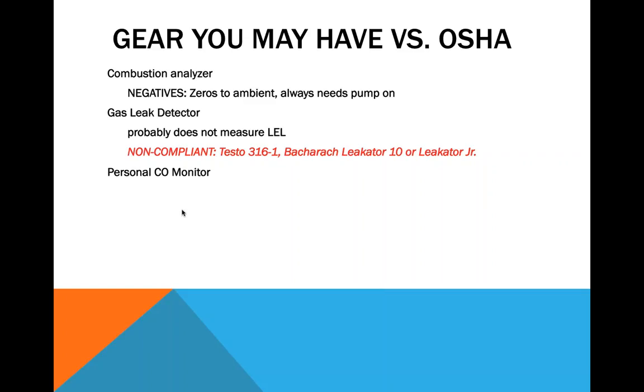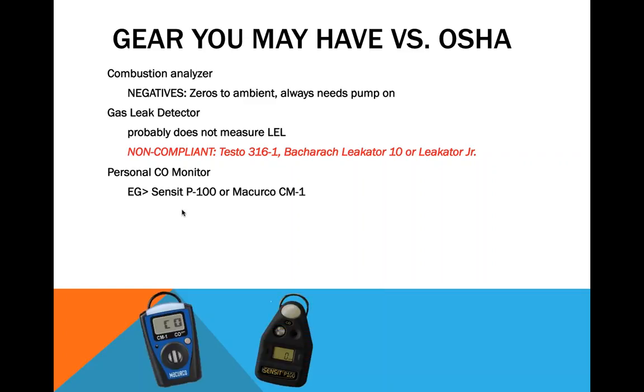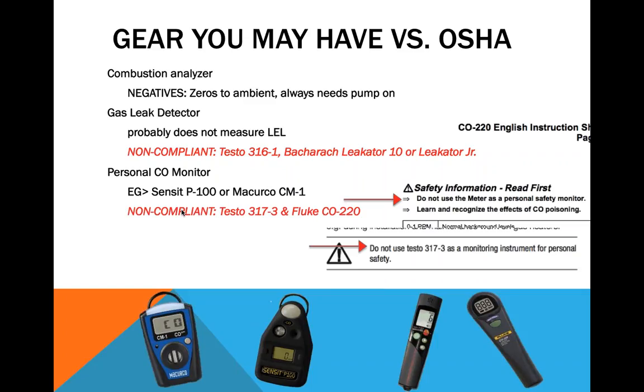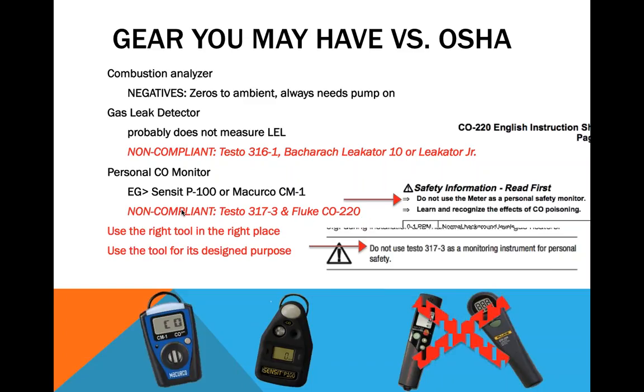Your personal CO monitor, your ambient CO monitor, things like the Sensit or the Macurco, these small devices are purpose-built for personal safety monitoring. They have lights, vibrating alarms, and audible alarms. They're designed to be rugged and used in the field for personal monitoring for CO. Non-compliant products like the Testo 317 and Fluke CO220 may not be used as a personal safety monitor. You can see here excerpts from the instruction manuals of these two products stating they're not to be used as a personal safety monitor. They can be used for ambient air detection, but not for personal monitoring. So the bottom line is use the right tool in the right place, for the purpose it's designed and built for.